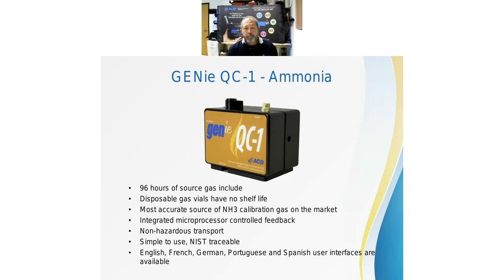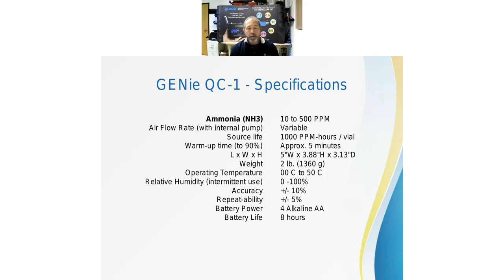And you see this variable output and flow rate. You get 1,000 ppm hours per vial. So you can start with your high range, say 500 ppm sensors, and then go around the facility and calibrate all your life safety sensors that may be set to calibrate at 25 or 50 parts per million. And again, you should get at least 8 hours out of the setup of batteries on this unit.